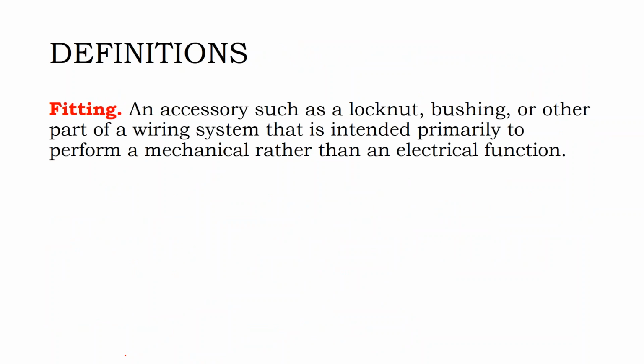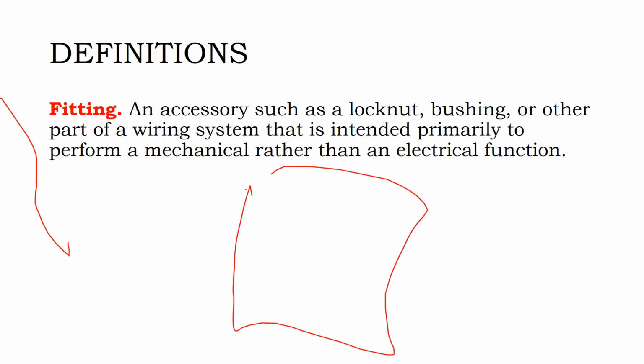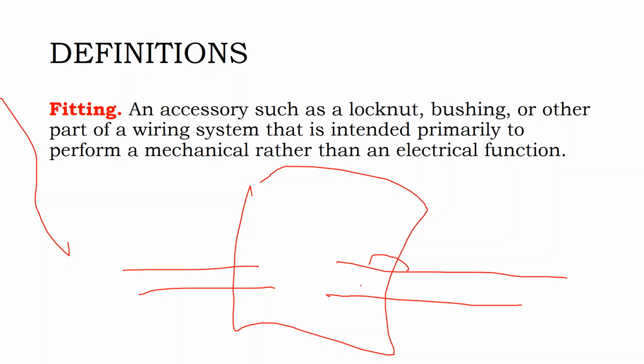So here's a definition: fitting, an accessory such as a lock nut, bushing, or other part of a wiring system that is primarily intended to perform a mechanical rather than an electrical function. And so we have a junction box, and you have a conduit going in one side, conduit going in the other side. Then you have all these different kinds of product for that penetration to be made. And it depends on if this box is a metal box or a plastic box, if this is PVC plastic conduit, or metal conduit.